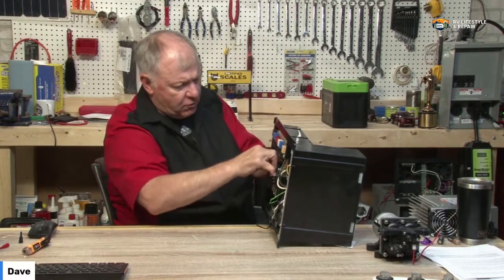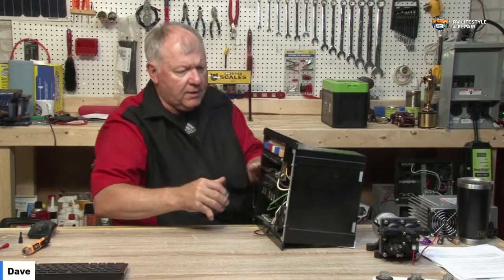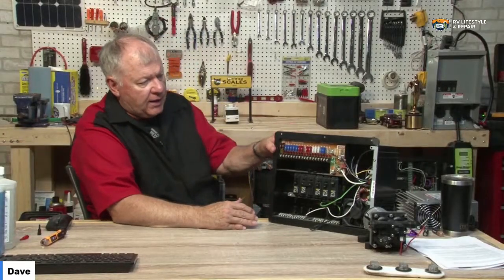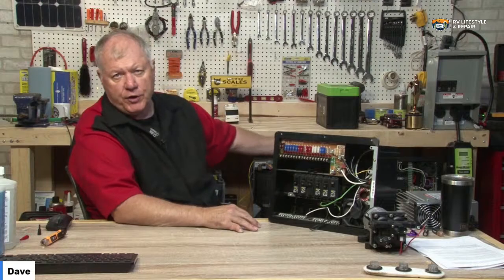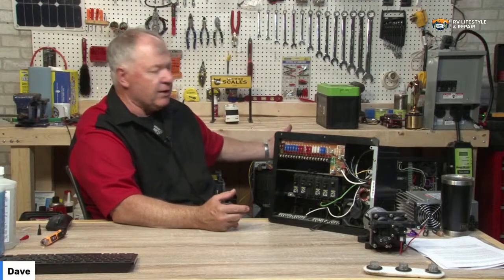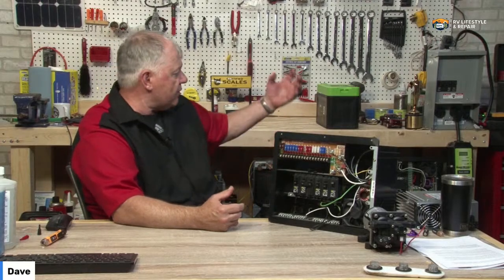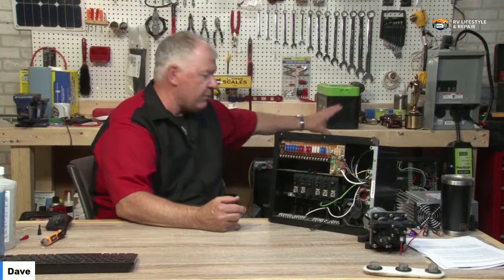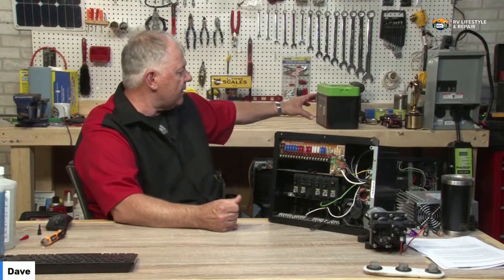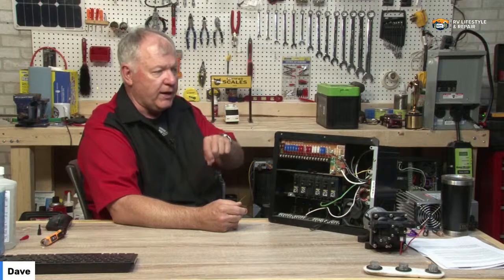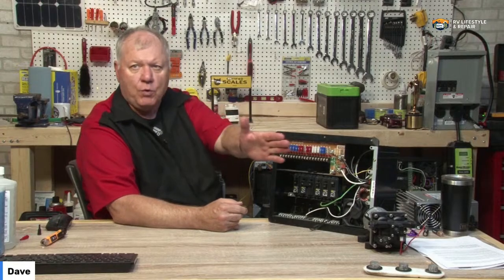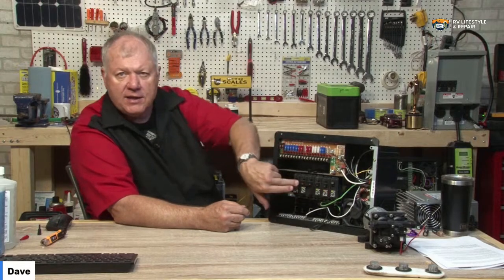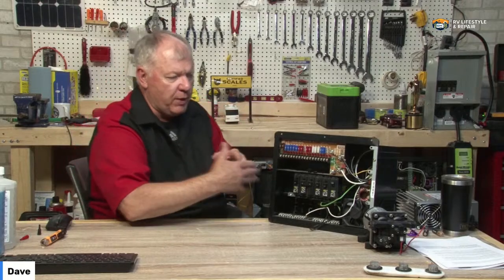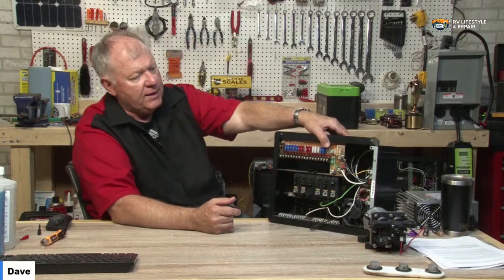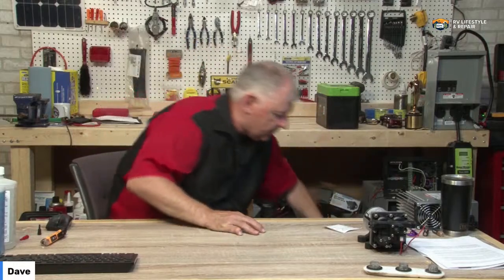That's also why sometimes when you do a 50 amp to 30 amp reducer, say you go into a park with only 30 amps available, and you get the step-down reducer for your 50 amp plug-in cord to 30 amp, it doesn't have the crossover. It only feeds one line to one side, so the other side won't work. You want the adapter that supplies the whole thing with 30 amps.